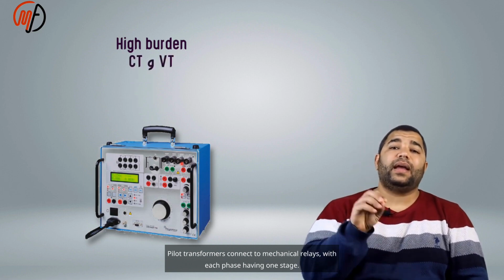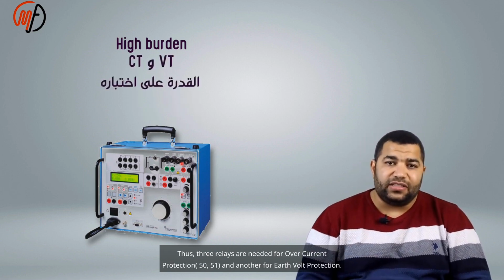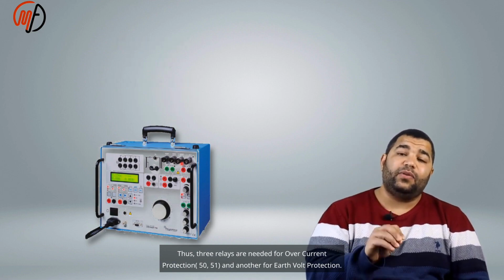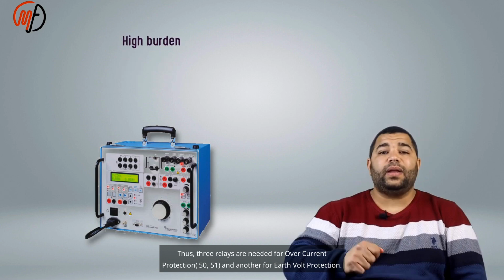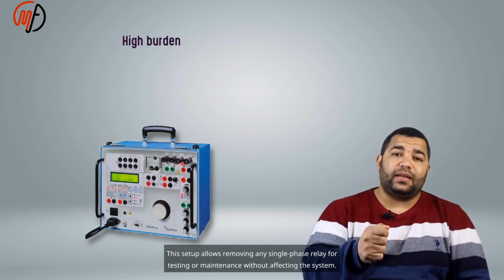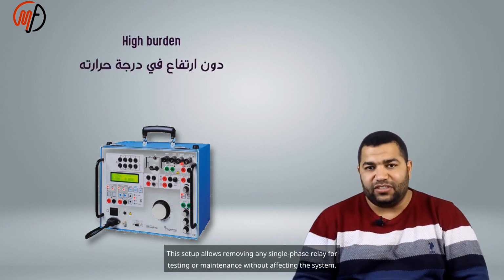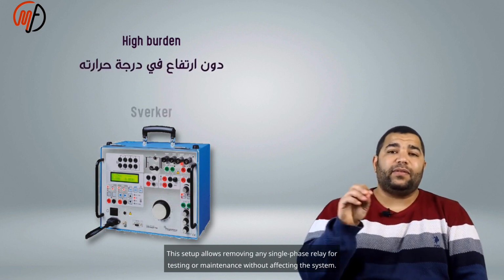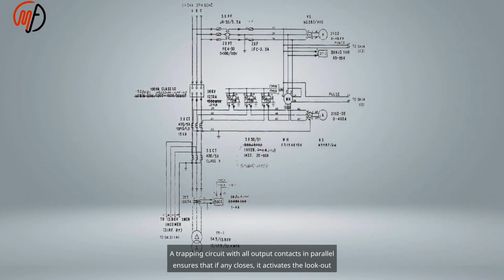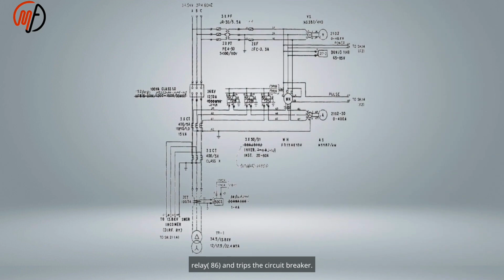We use a resistor. Pilot transformers connect to mechanical relays, with each phase having one stage. Thus, 3 relays are needed for overcurrent protection, 50, 51, and another for earth fault protection. This setup allows removing any single-phase relay for testing or maintenance without affecting the system. A tripping circuit with all output contacts in parallel ensures that if any closes, it activates the lockout relay, 86, and trips the circuit breaker.